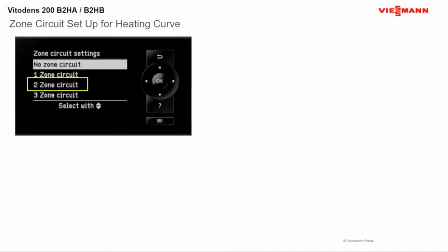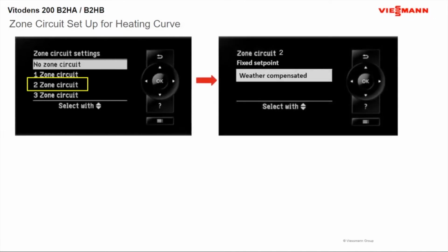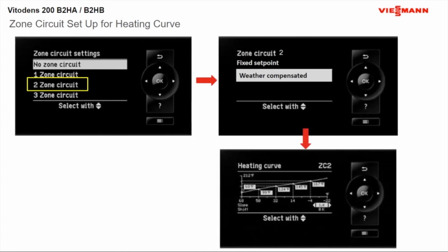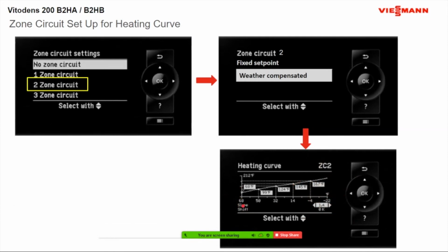Now we're going to do zone circuit 2. For this example here, we're going to pick weather compensated. Next question it asked, set up your heating curve. Remember, we're defaulted at the 1.4. So if you want hotter temperatures at your coldest day of the year, you're going to adjust that 1.4 up. And don't forget about your 0 Kelvin if you want to make any type of shift at the bottom end of your scale. You can also reduce that bottom end of the scale. So say you're getting solar gain at your lower temperatures, you can lower that down at your lower end of your scale so it will go off sooner.